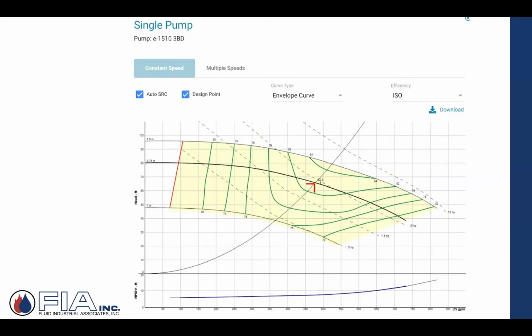So then you say, well, why would I ever do that? Well, in reality, if I'm doing a process and I'm taking water from a vat, going to whatever that is, and back, and it never changes, I could probably do duty point and be perfectly fine and safe. But if I'm taking this 475 gallons a minute and feeding a whole bunch of fan coils that are distributed through a piping network, and they have control valves opening and closing, and I'm relying on a balance contractor to go in and balance this thing perfectly, and it may or may not happen, it's a very strong possibility that that pump may be drifting left or right of that duty point.